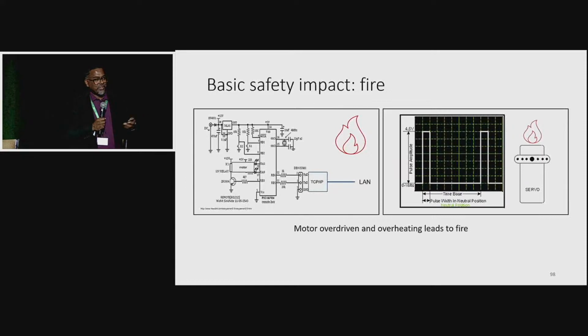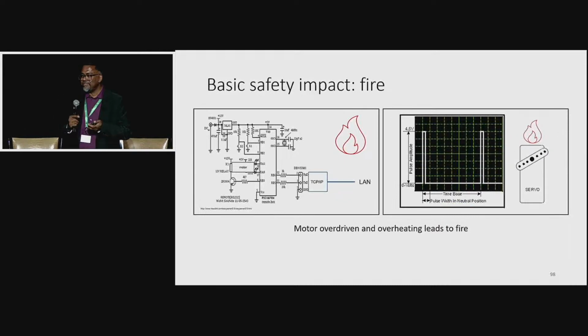We have a long 100-plus year history of protecting devices from catching on fire. But now, with cyber devices, you could actually get into a device and allow it to try to move the motor, but without turning that electrical energy fully into mechanical energy to cause rotation of the motor, by disabling some of the motor windings through software. If you do that, you end up with a coil, a motor winding, that you're sending energy to. That energy is not getting dissipated as mechanical movement. Instead, you're creating an inductive heater. That heater starts heating up, your ventilator starts heating up, you exceed the plastic flame ratings, and next thing you know, your device is on fire.